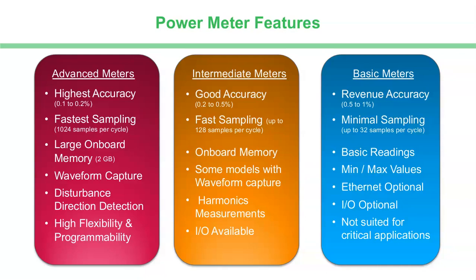rate. So you have analog voltage and current waveforms that are being sampled and converted from analog to digital inside the meter. And the faster the meter does that, the more accurately it's able to create that sinusoidal waveform, plus any harmonics that are distorting that. And so you can see the fastest sampling meters are generally around 1024 samples per cycle, not seconds. So it's very, very fast.